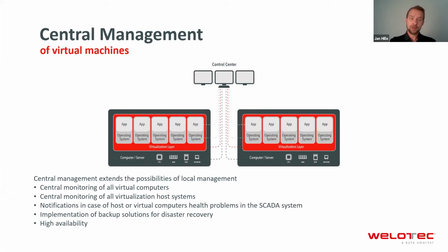What's another interesting point? We said before we can copy or import or export virtual machines. With the central management, we can also implement real backup solutions, which take care of scheduled backup and backup management. We can, for example, say, please back up all my virtual machines. So all the appliances, the HMI, the gateway, the log server, please back up those machines every night at, for example, 1 a.m. And please keep 7 weekly backups, 7 daily backups, 1 yearly backup. So we have a real backup management and backup history.